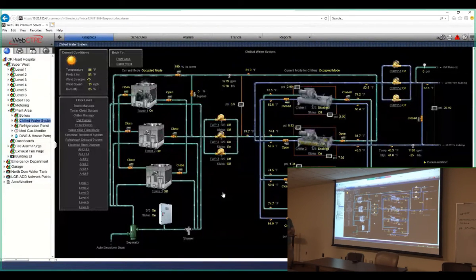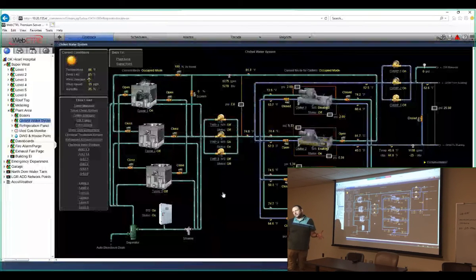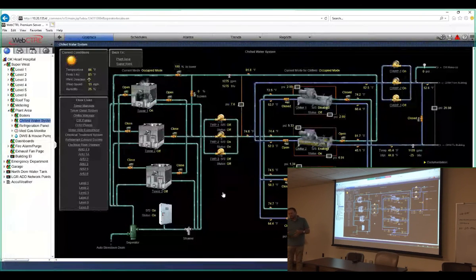Typically, on the sequence of operation, and Corey's going to go through this on the central plant, the majority of the time you're probably going to need one chiller. These chillers really can keep up with the load pretty good. Last week, or the other day, when we got into the mid-90s and upper 90s, we had to have 2 machines to run. They kicked on and ran, but right now we've only got 1 machine running. It's able to maintain set point.